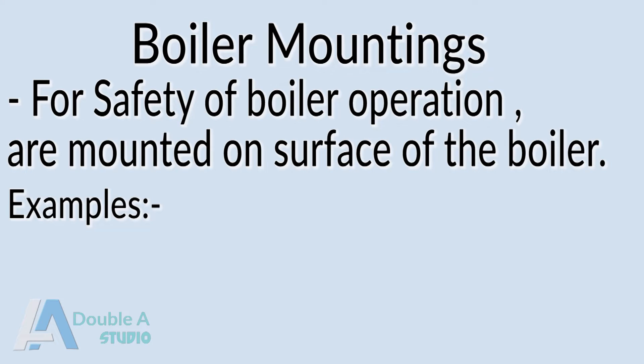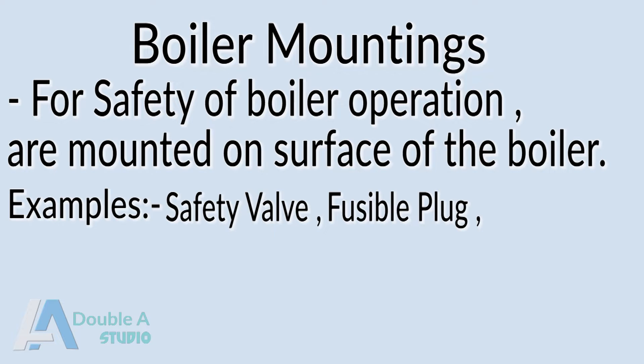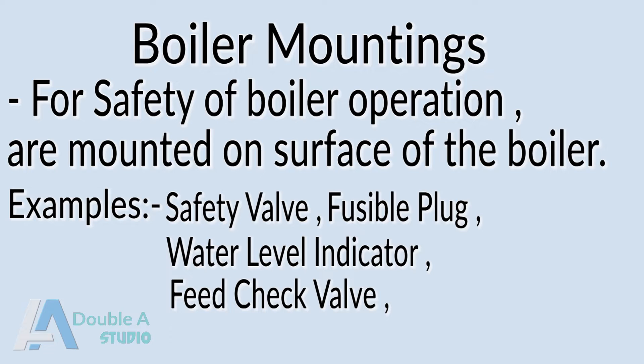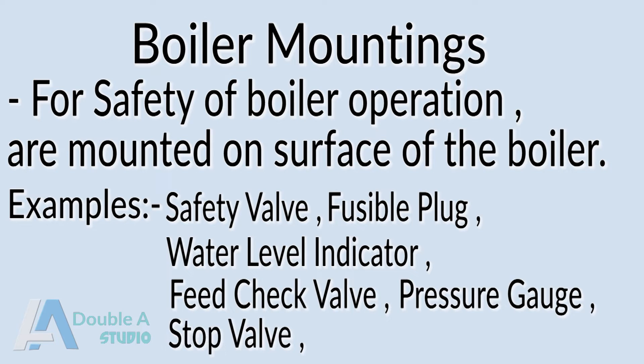Parts of the boiler can be broadly classified into two types: mountings and accessories. Boiler mountings are components used for ensuring the safety of the boiler operation. These are generally mounted on the surface of the boiler, such as a safety valve, fusible plug, water level indicator, feed check valve, pressure gauge, stop valve, and blow-off cock.